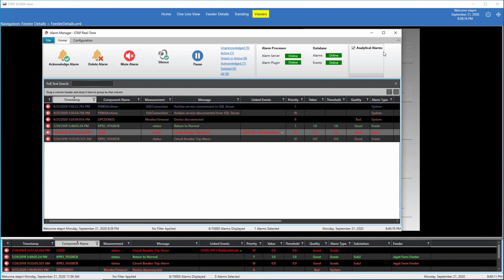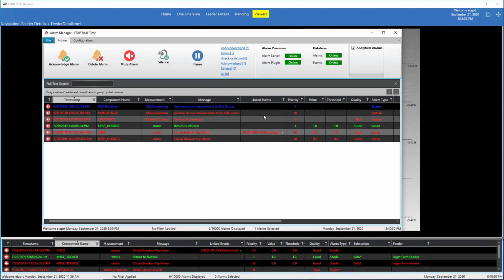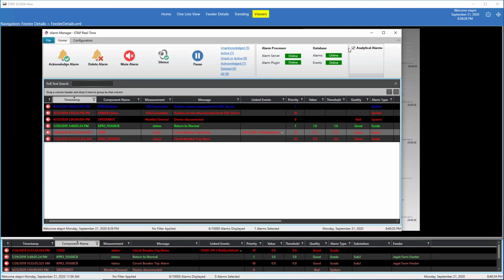One key factor to notice in ETAP is the analytical alarms. This is very unique to ETAP software. In addition to monitoring the status of circuit breakers and generating an alarm when they trip, or looking at set points and bringing in an alarm if a set point is exceeded, the system is also performing analytical alarms. That means it's looking at the capacity of the transformers, the capacity of the feeder lines, and the voltage levels at the bus levels. If any of those components, for example, the capacity gets exceeded or the voltage goes above or below acceptable levels, the software will generate its own alarms.